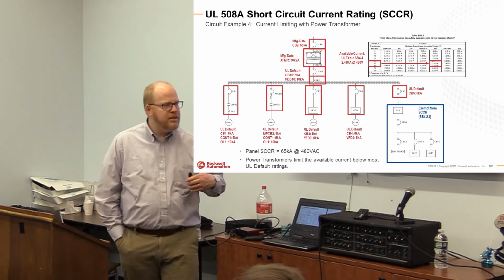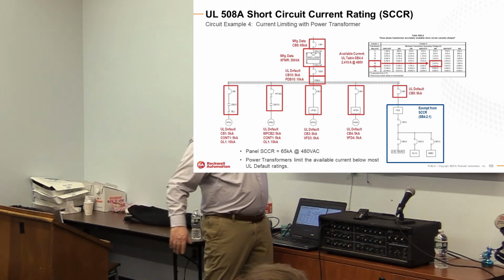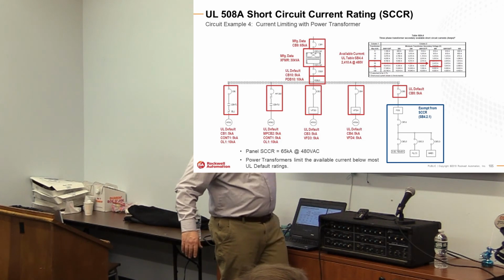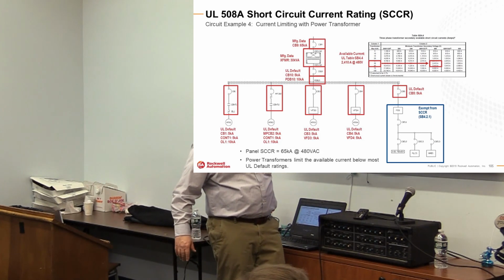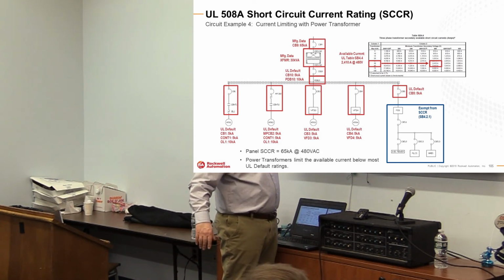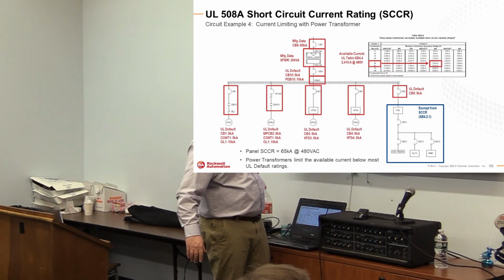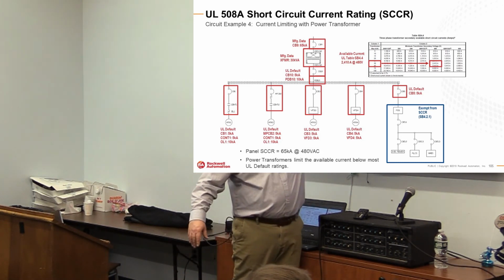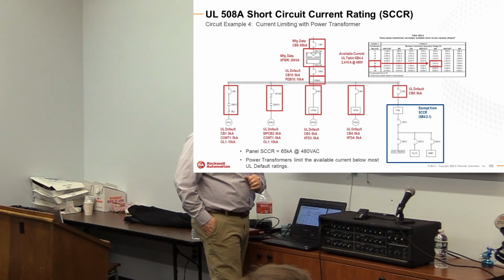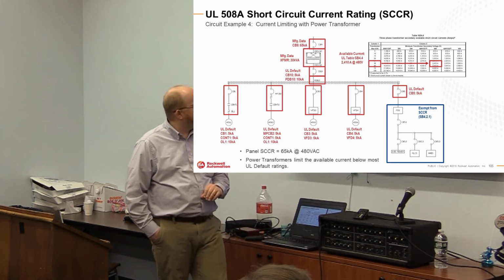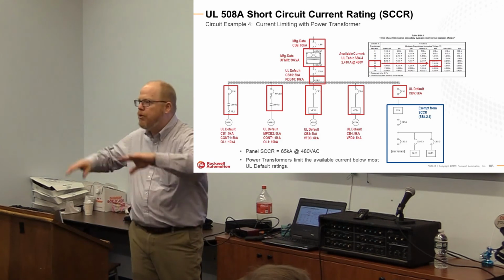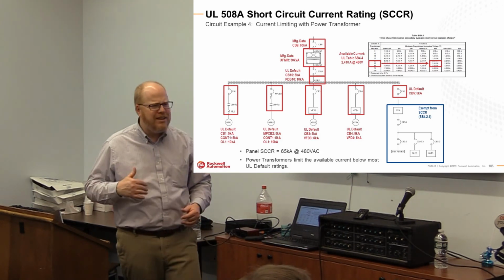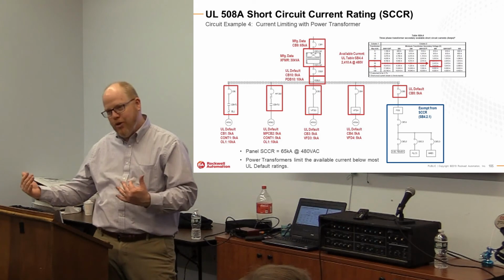So the power transformer is kind of the simplest one, because like we had said in the chart, you look at the power transformer and you just look at what its peak let through is, and they're very, very limiting. And so you basically just put a power transformer in front of everything, so even if you had to use a 5 kA panel in this case, you would be fine because the available let through is 2.4 kA. So in this particular scenario, I'm talking as if I put a transformer inside a box. So I'm looking inside the panel. Of course, somebody in my other class said, that'd be a pretty big transformer to put in a box. I mean, yes, it would.